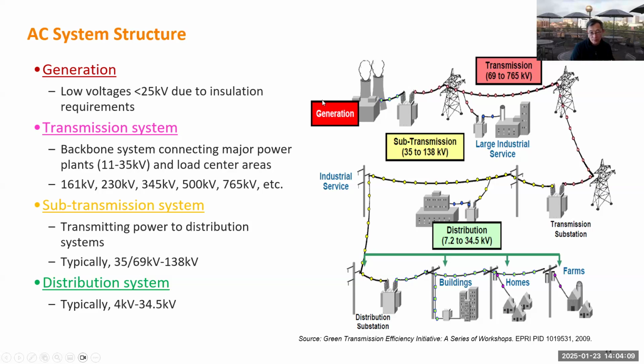Usually this part of the system is operated at a lower voltage. By lower voltage, I'm not talking about something like 130 volts. It's 23 kV, which is lower than the transmission voltage level, because in order to maintain low cost of manufacturing and maintenance for the generators, we don't want to increase the insulation cost. So it's better to operate at a voltage much lower than transmission voltage, usually lower than 25 kV.